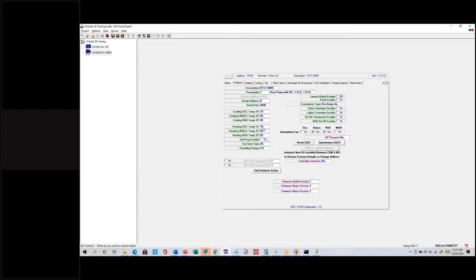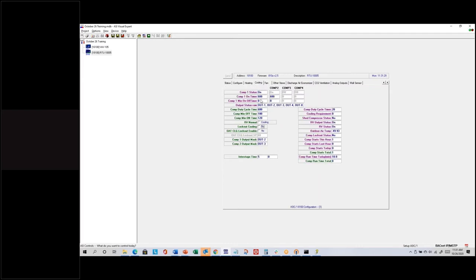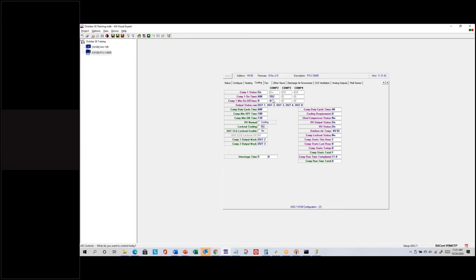I need to lower my set point further to get this below 100 percent. I'll lower it to 74 — that should definitely start ramping down. I just want to show that on-times will calculate and adjust accordingly. At 96 percent cooling requirement, on the cooling tab I can see compressor 2 only wants to run for 552 out of 600 seconds. Compressor 1 still wants to run indefinitely because it will as long as the requirement is above 50 percent.